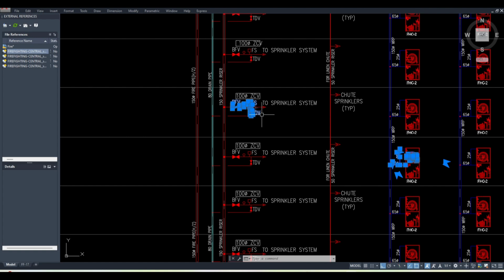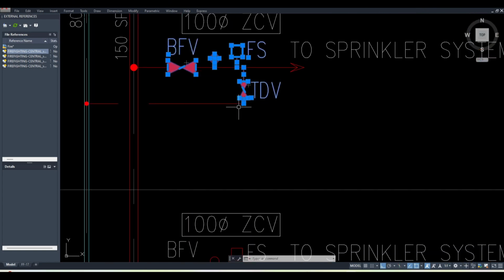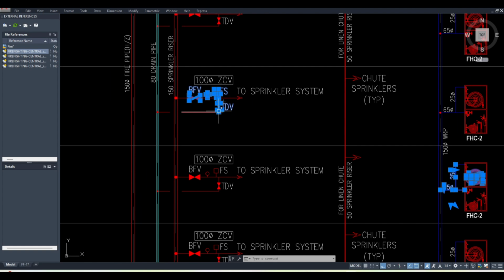Here we need two fire zone control valves. It cannot be handled by one zone control valve. Then the zone control valve must be installed in an accessible location. That also you can check. Then this zone control valve assembly can be within only 600 mm distance, and then it must be connected with the riser, and a drain point must also be provided. This drain line, while considering the drain point, you can see that your pipe should not go up and down, up and down, up and down, right? That also you can see.